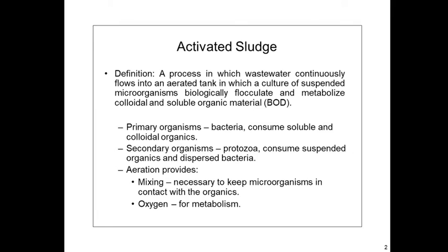Activated sludge process: a process in which wastewater continuously flows into an aerated tank in which a culture of suspended microorganisms biologically flocculates and metabolizes colloidal and soluble organic material, BOD. Whatever solid or organic matter is present in that wastewater is utilized by microorganisms and converted into simpler matter. That process is called oxidation.